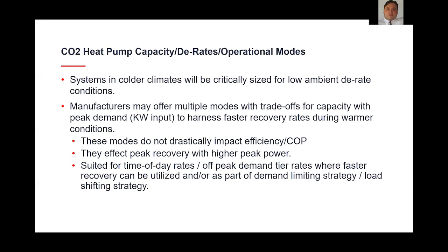Oftentimes manufacturers may offer multiple modes, and you'll see that published. Mitsubishi offers this as well with our heat pumps, and these offer different peak output capacities, and they'll be labeled or described as maximum capacity versus energy save type modes. But really, these are just trade-offs under higher ambient conditions to achieve higher recovery rates at the expense of higher peak kW inputs. So when you see different mode options like this, they're more suited for time of day rates, off-peak demand tier rates, where you can utilize this faster recovery, or be part of a demand limiting or load shift strategy, where you may have load up periods where you store hotter water temperature in the summer, and then demand limited periods where you're load shedding.